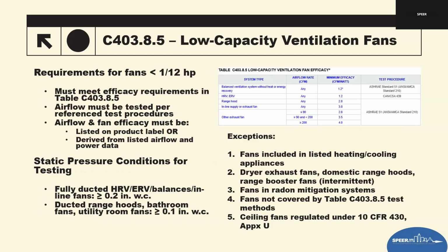They are now addressing the low capacity ventilation fans. Before it was just showing for those large kitchen vent hoods and things. Now it's lower ones. So for small capacity mechanical ventilation fans, those motors that have under 1/12 horsepower, which also can include things like bathroom exhaust, inline fans, utility room fans, low capacity ERVs or HRVs. The 24 now requires standardized testing and minimum fan efficacy levels to ensure these smaller fans perform efficiently and consistently. Same thing we have in the residential side.